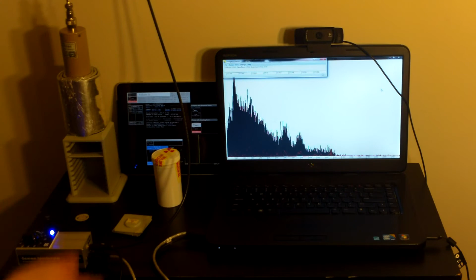It goes to this, and basically whenever a gamma ray hits the crystal, it produces a small flash of light, right? That flash of light, I think it's in the ultraviolet range, hits the photocathode, which produces a burst of electrons, and the number of electrons it produces is proportionate to the intensity of the light, the number of photons produced. So gamma ray hits, produces photons, hits material that produces electrons. They get pulled down this tube here, a photomultiplier tube, and they get accelerated by the photomultiplier tube, producing a voltage, a current, which is proportionate to the number of electrons, which is proportionate to the number of photons, which is proportionate to the energy of the gamma. It all stays proportional. It's kind of interesting.